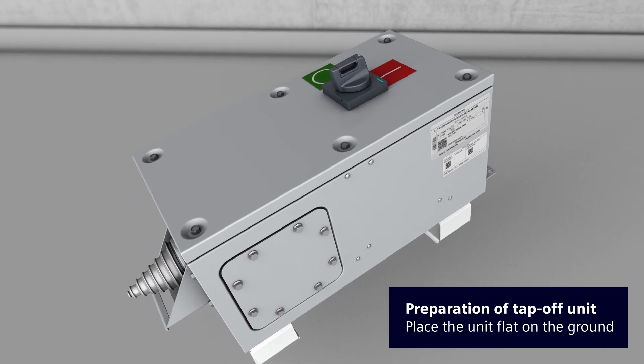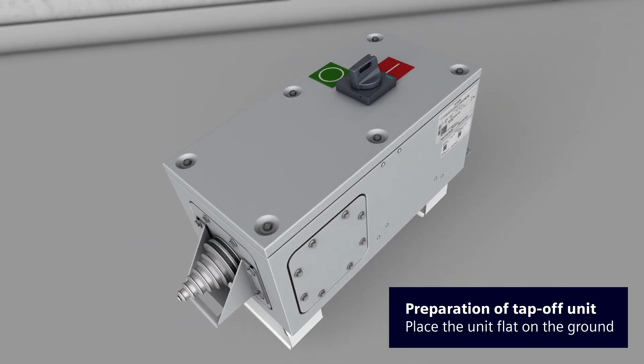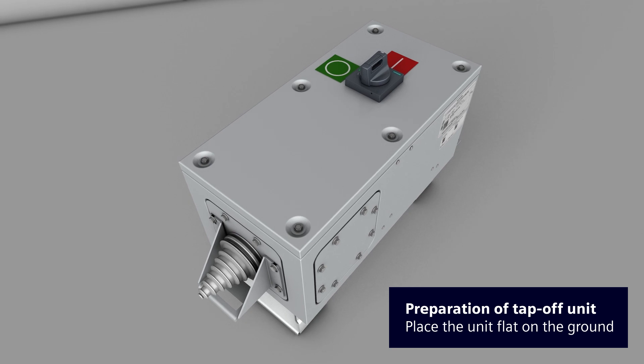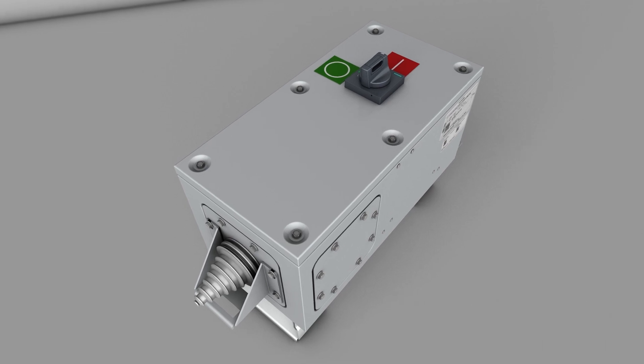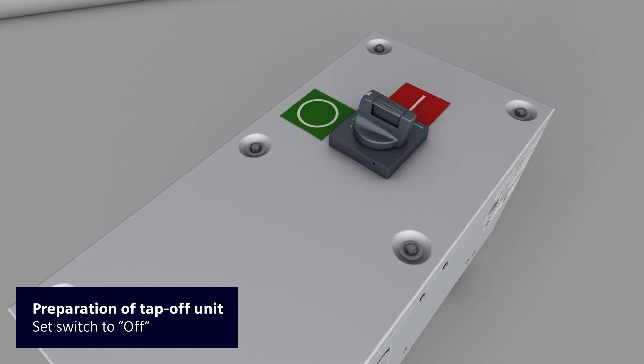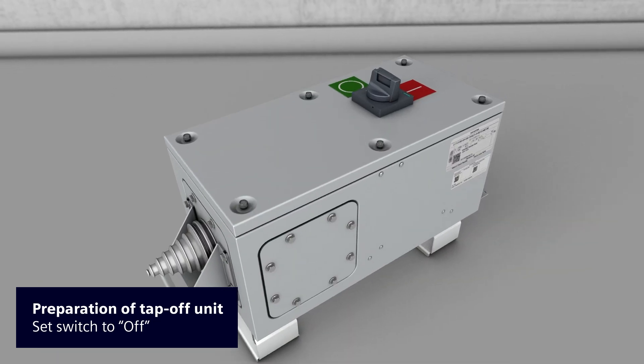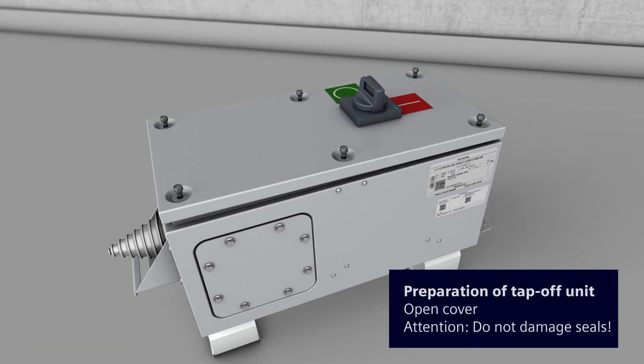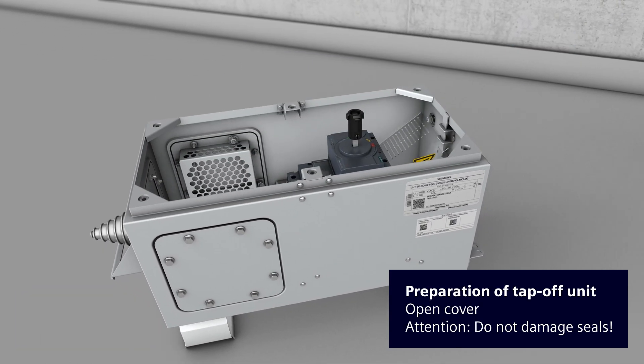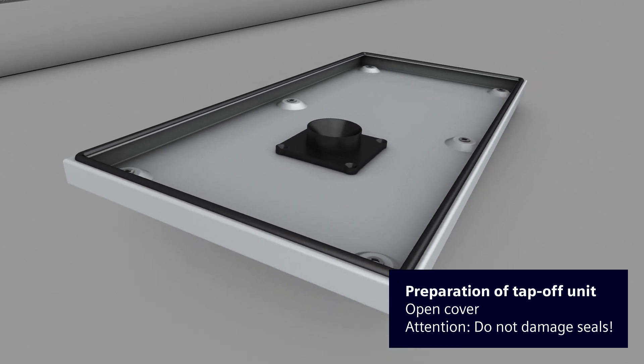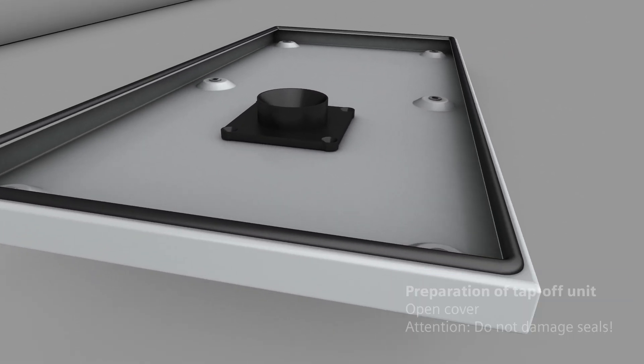Prepare the tap-off unit for installation. Place the tap-off unit flat on the ground. Set the switch position of the door-mounted rotary operator to off before removing the cover. Detach the cover screws and lift off the cover. Make sure not to damage the seals arranged on the inside of the cover.